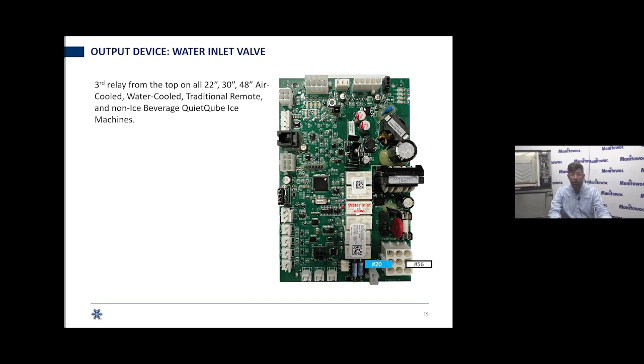Hey, you turned off the water valve supplying the machine, you took the line off, turned the valve back on and filled the bucket. Okay, you've got water. Now you know the water inlet valve is either plugged up and needs to be cleaned or needs to be replaced. And if you don't have power and you do not have a water probe that's telling you you already have water, either by utilizing the input menu in real-time data or by looking at the lights for the low and high water probe, not sensing on the screen, no lights lit on the board, no power from the relay, well, now you know that the relay on the board is what's your issue. You'd replace the board. But if you've got power and no water, well, the board's doing its job. It's calling, and it's just not giving you any.